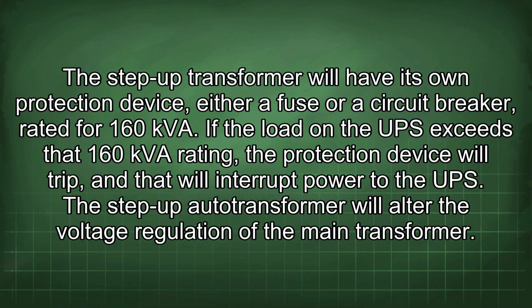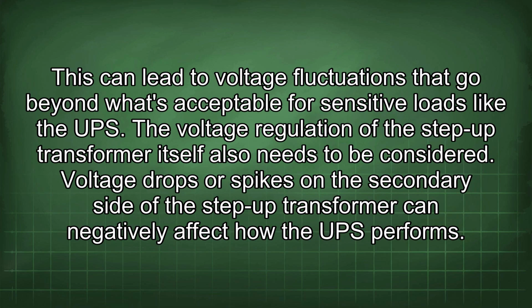The step-up transformer will have its own protection device, either a fuse or a circuit breaker, rated for 160 kVA. If the load in the UPS exceeds that 160 kVA rating, the protection device will trip, and that will interrupt power to the UPS. The step-up autotransformer will alter the voltage regulation of the main transformer. This can lead to voltage fluctuations that go beyond what's acceptable for sensitive loads like the UPS. The voltage regulation of the step-up transformer itself also needs to be considered. Voltage drops or spikes on the secondary side of the step-up transformer can negatively affect how the UPS performs.